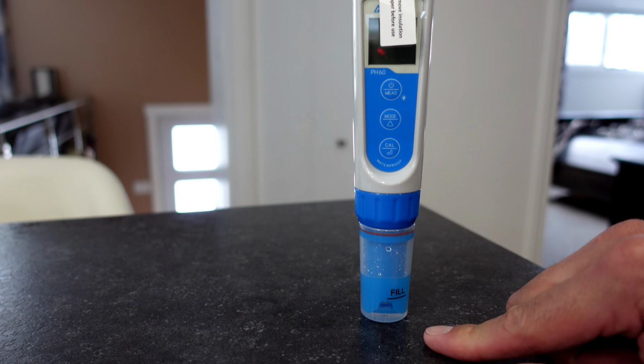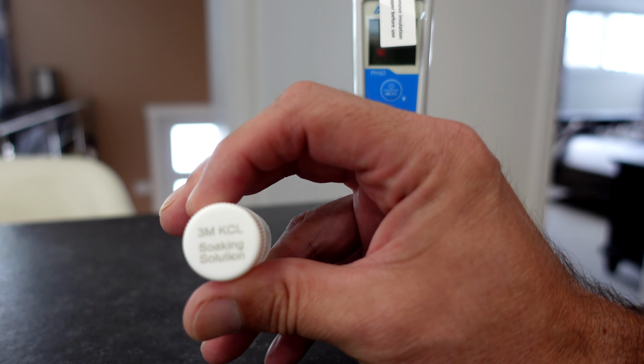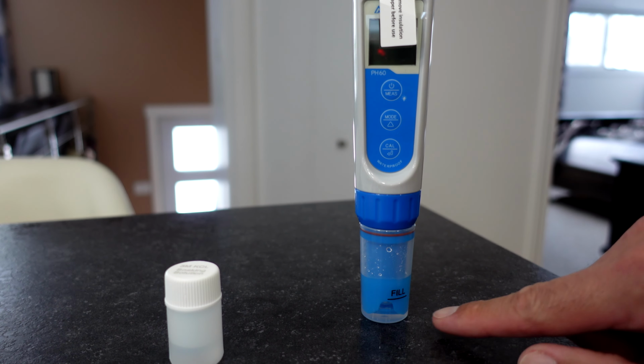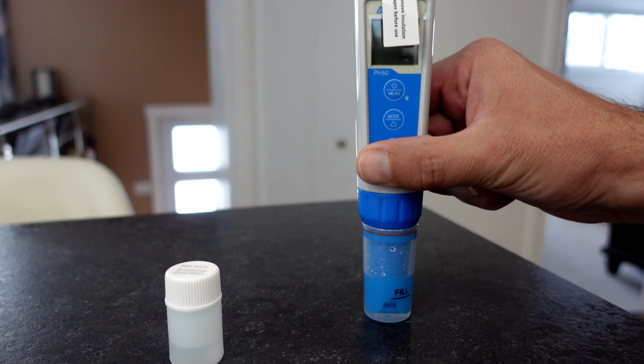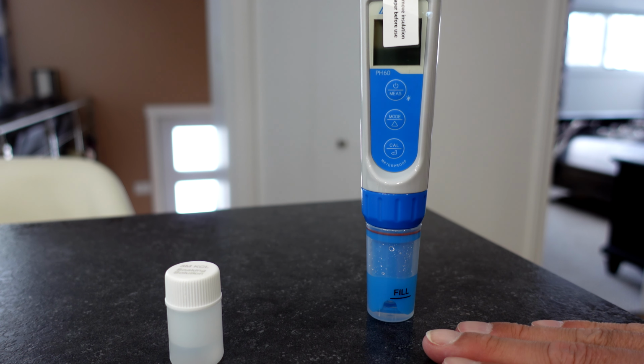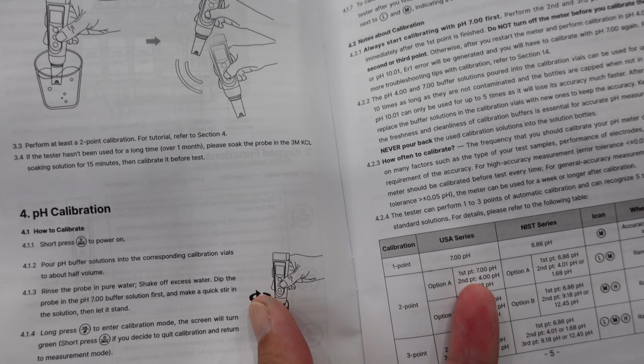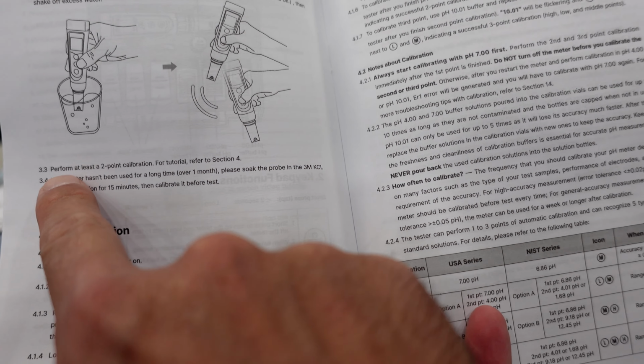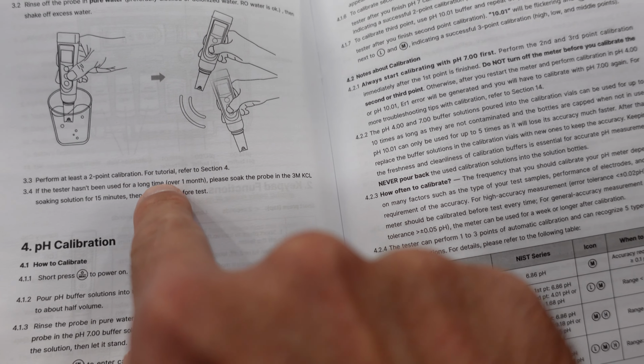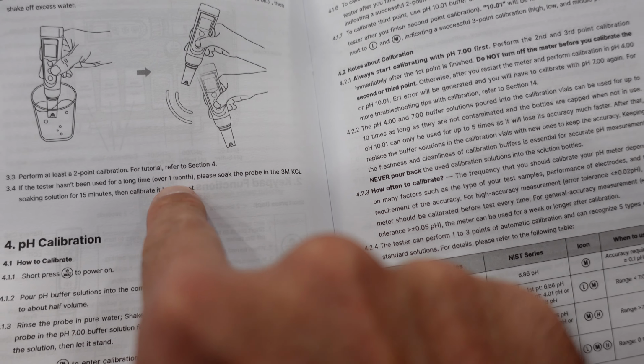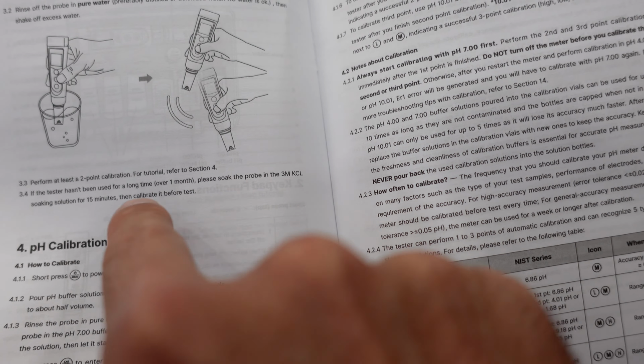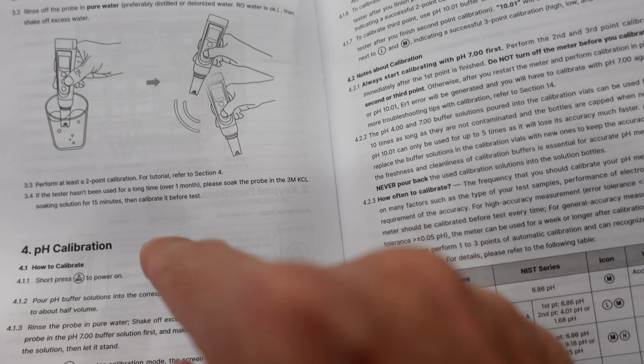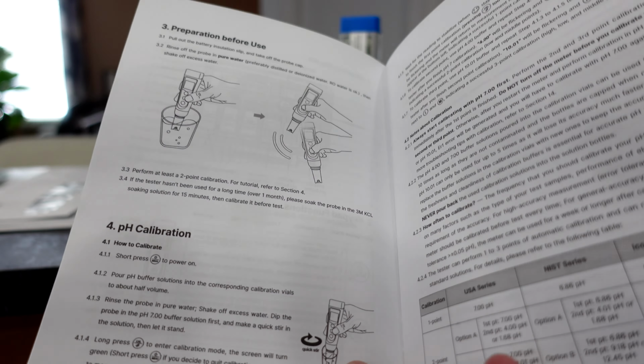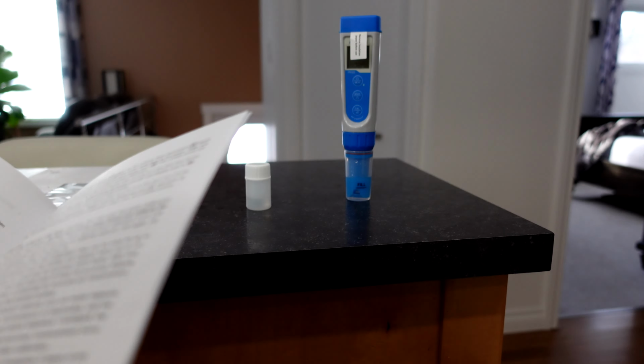All right, so the first thing I'm doing with mine is taking the stock solution, and I filled it to the line, stuck the probe in there, and I'm going to leave that like that for 30 minutes. Now, the reason I decided to do that is because of this in the instructions. If the tester hasn't been used for a long time, over a month, please soak the probe in the 3M KCl solution for 15 minutes and calibrate before test.